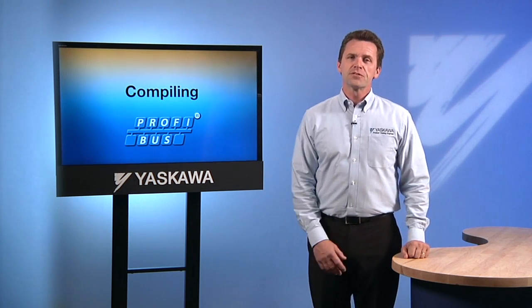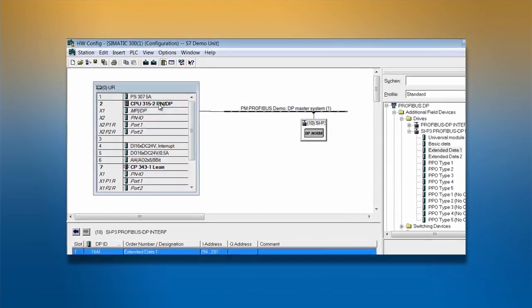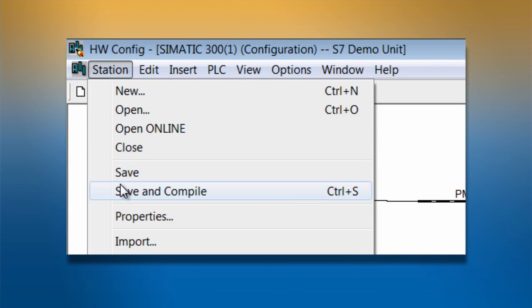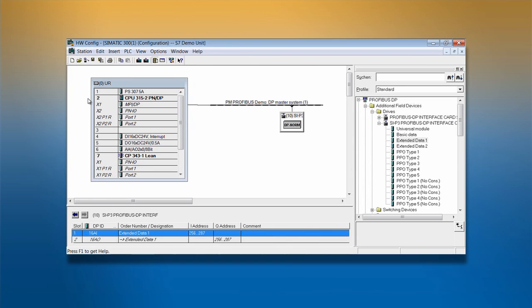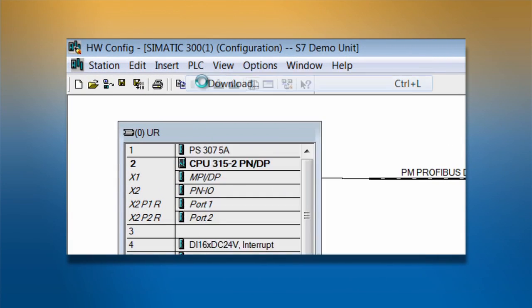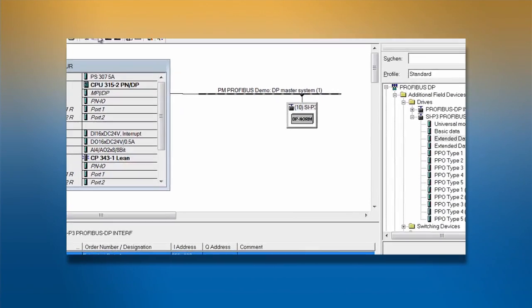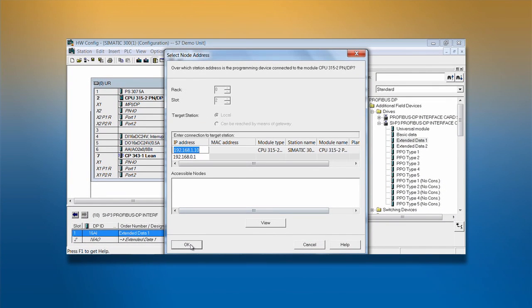Now that the configuration is finally set, we need to compile the configuration so that it can be loaded into the PLC. To do this, we pull down the Station menu and select Save and Compile. This saves the configuration onto our computer and compiles it so that it can be downloaded from the computer into the PLC. Our compiled file can now be used to download into the PLC. Go to PLC and click Download to start the download into the PLC. The next step would be to create a variable table to test communications.